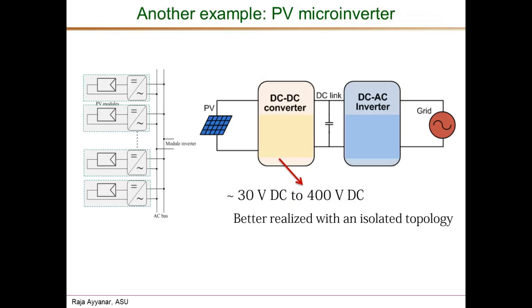Many utilities still demand a transformer here, but newer codes, the NEC codes, do allow transformer-less PV inverter topology, so it is allowed. But even though it's allowed to not have a transformer, for this application it may be preferable to use one because of the large step-up conversion ratio. You may be able to implement this with multiple stages of a boost converter, but using an isolated converter would result in better efficiency and better power density compared to a non-isolated solution.